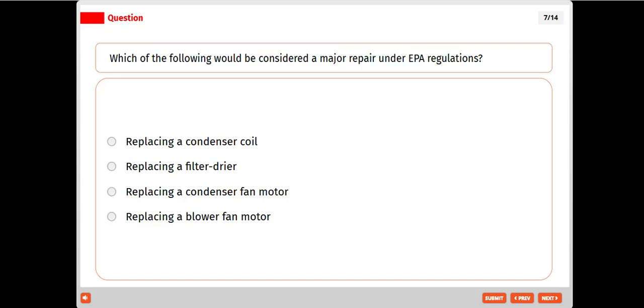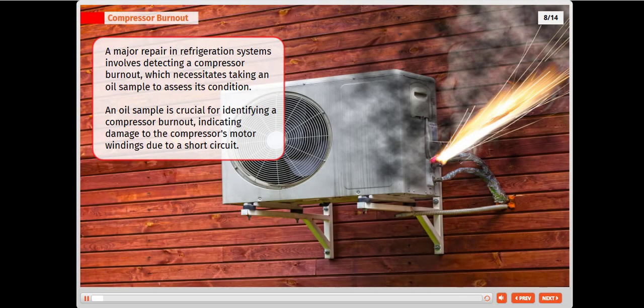Which of the following would be considered a major repair under EPA regulation? Replacing a condenser coil? Yeah. A major repair in refrigeration systems involves detecting a compressor burnout, which necessitates taking an oil sample to assess its condition. An oil sample is crucial for identifying a compressor burnout, indicating damage to the compressor's motor windings due to a short circuit.